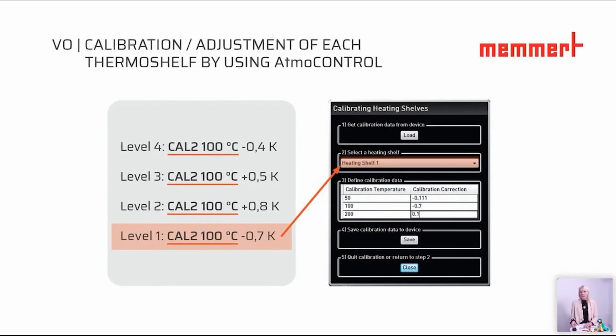This feature with nitrogen, by the way, is a premium module version. So that is an option that you can operate a vacuum oven with this inert gas. And now a next feature, which is also mostly advantageous for most professional uses: you can do this calibration of each thermo shelf. That means we have the AtmoCONTROL software. On the AtmoCONTROL software, that is also what you see on the screen in the picture, we have here the possibility to choose the shelves.